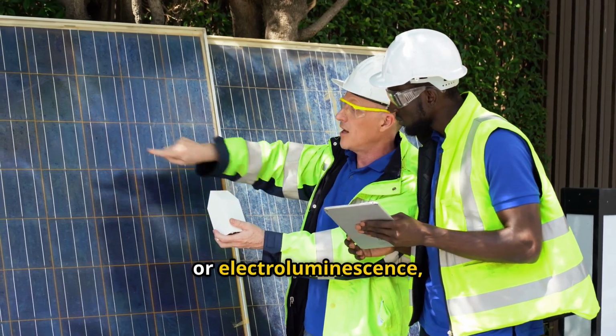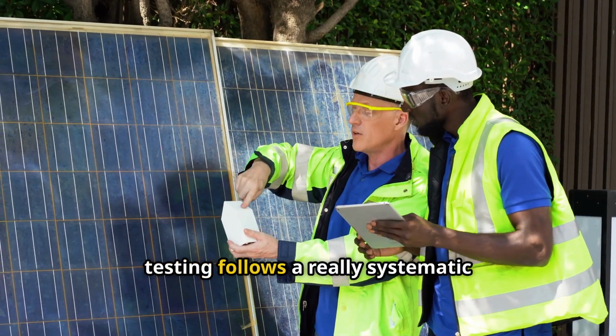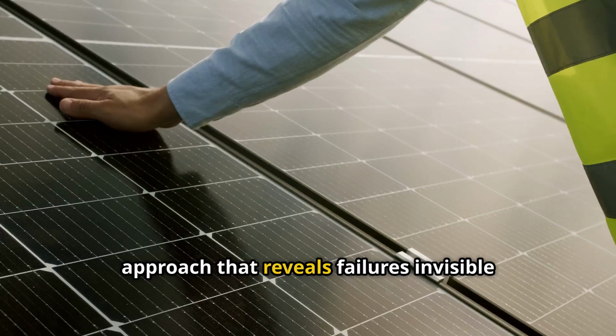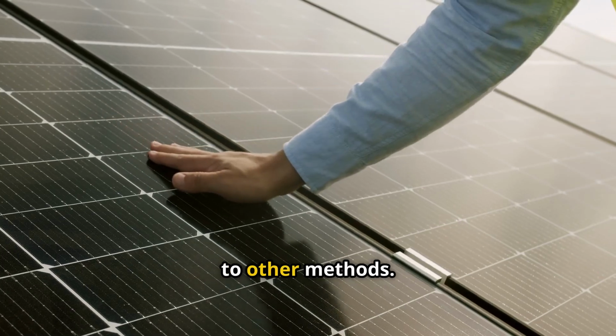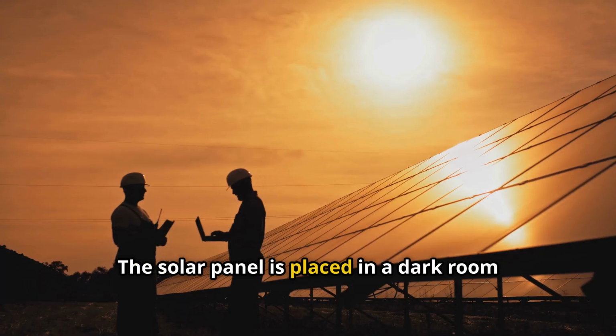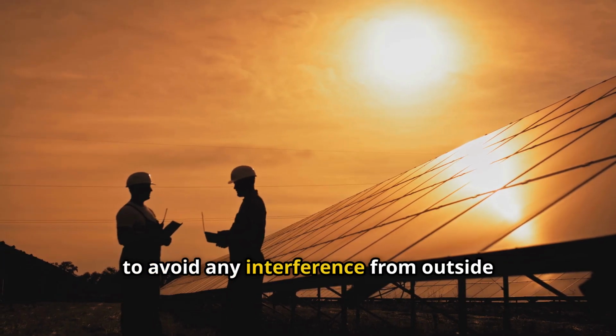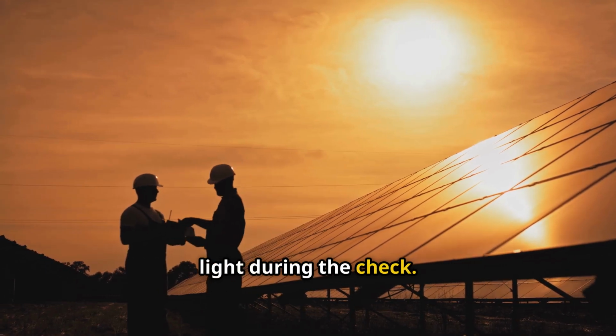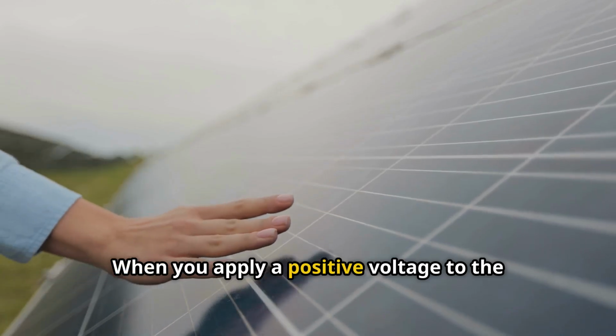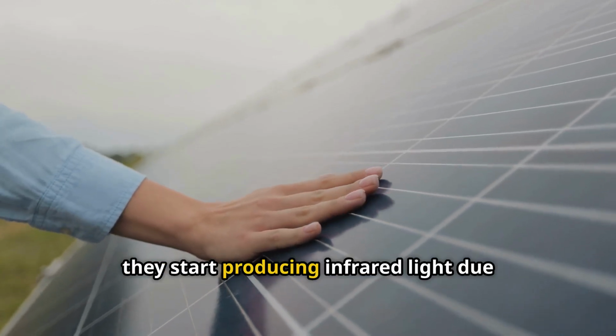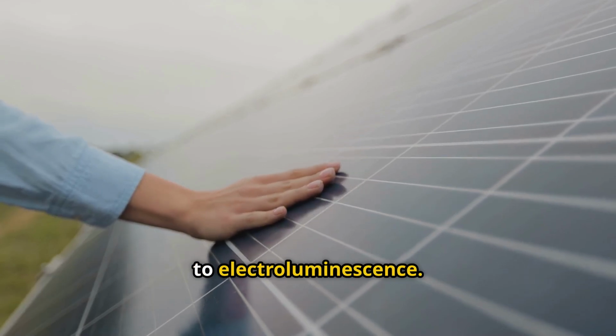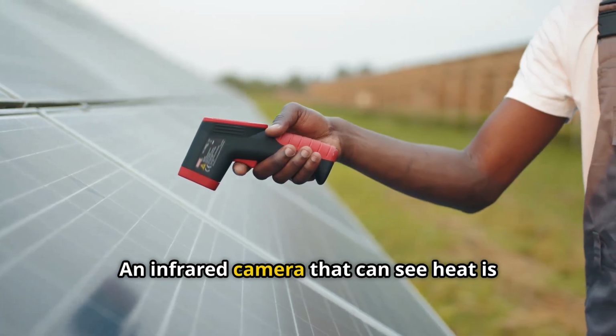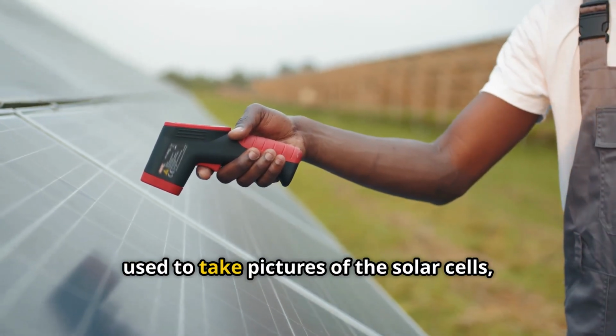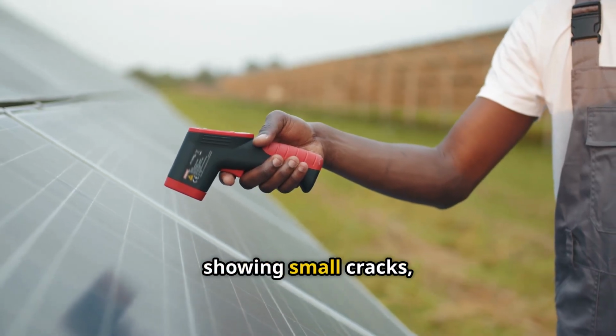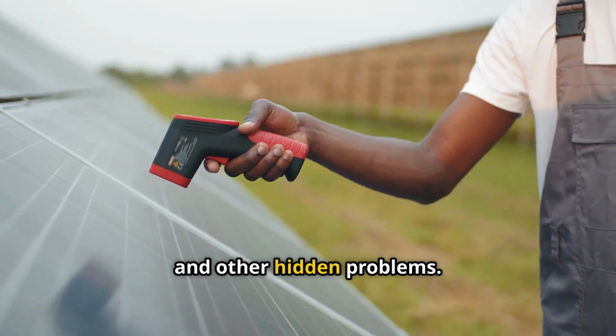Professional EL, or electroluminescence, testing follows a systematic approach that reveals failures invisible to other methods. The solar panel is placed in a dark room to avoid interference from outside light. When a positive voltage is applied to the solar cells, they start producing infrared light due to electroluminescence. An infrared camera that can see heat takes pictures of the cells, showing small cracks, broken cells, and other hidden problems.